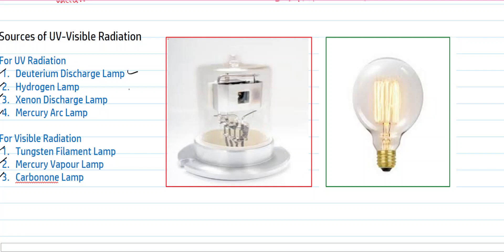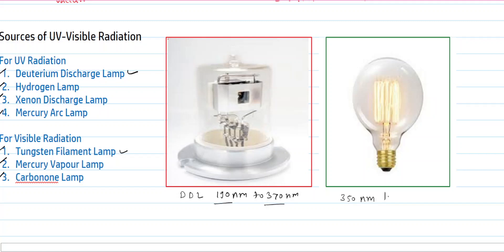The deuterium discharge lamp and tungsten filament lamp are generally used in ultraviolet and visible spectroscopy. The deuterium discharge lamp operates at a wavelength of about 190 to 370 nanometers. The tungsten filament lamp produces visible radiation with a wavelength of about 350 to 2000 nanometers. These two lamps are generally used in ultraviolet and visible spectroscopy.